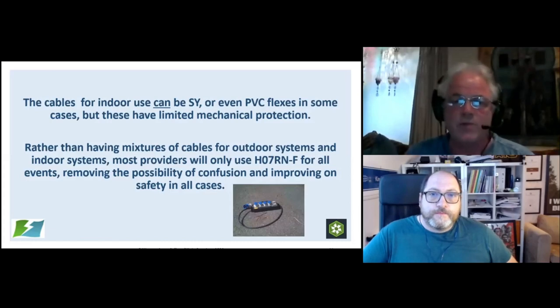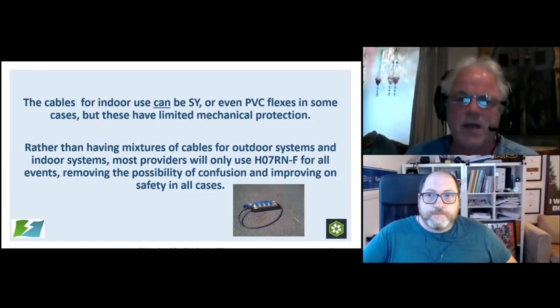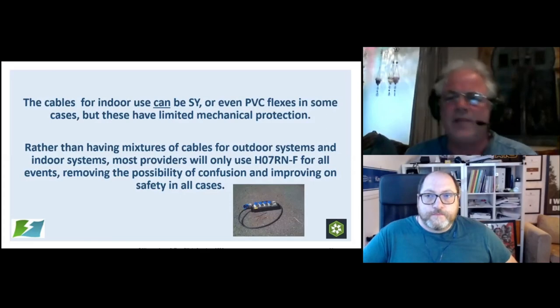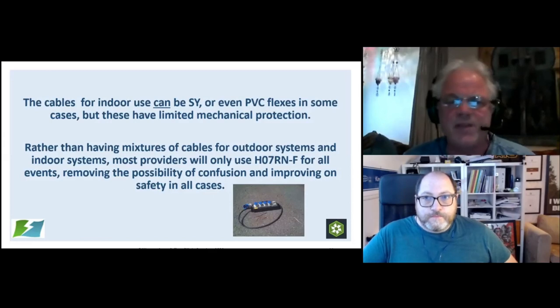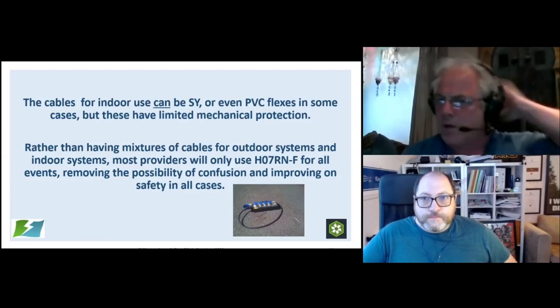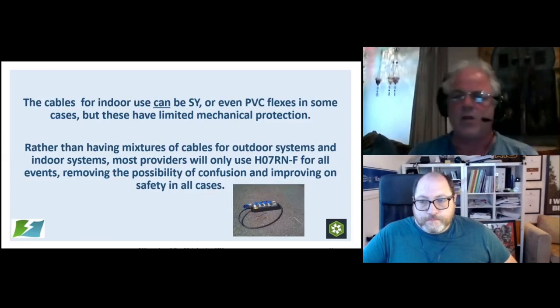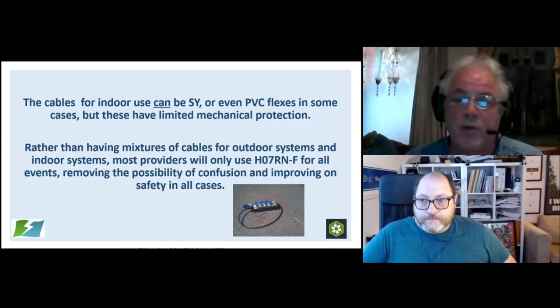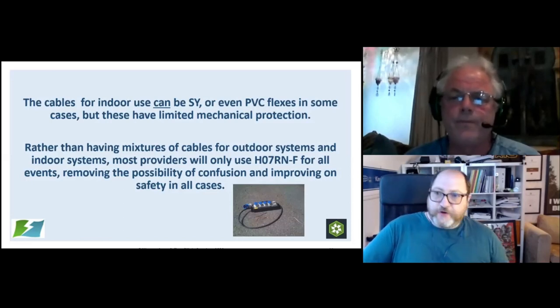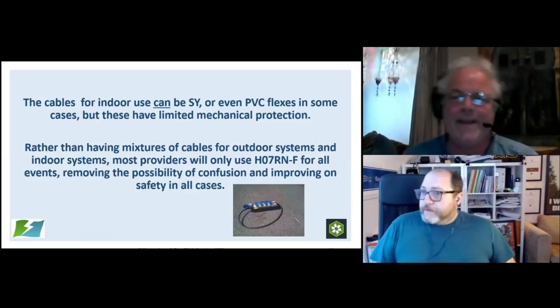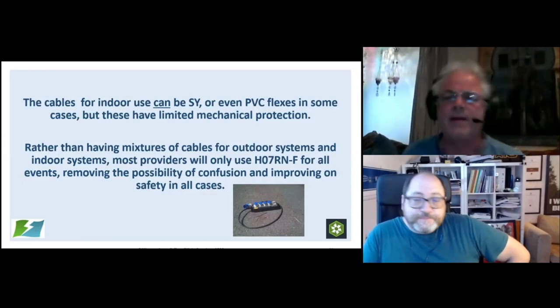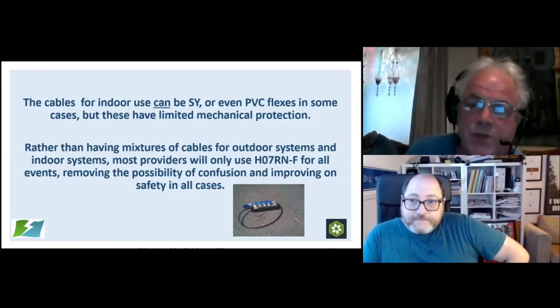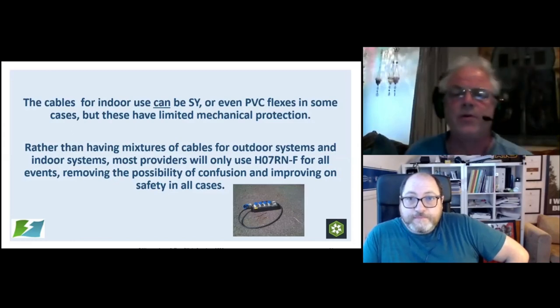As I said, indoor cables can be SY, which is the braided flex, and PVC flexes. But again, with the SY, remember that it should be terminated properly using the proper gland, otherwise it makes it unusable. So I don't like to see that. It's better off for fixed equipment. PVC flexes, Arctic Blue was the common one that was used for years and years, and people had a huge stock of it. You still see people bringing it out and dragging it out. It's when your stock gets thin that it starts to come out as well. But it's one of those where, no, we shouldn't be using that. You can use it indoors, but not outdoors.